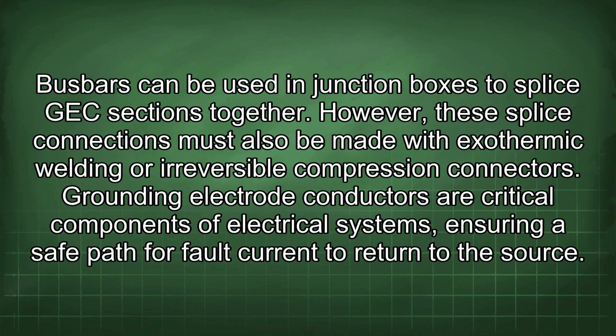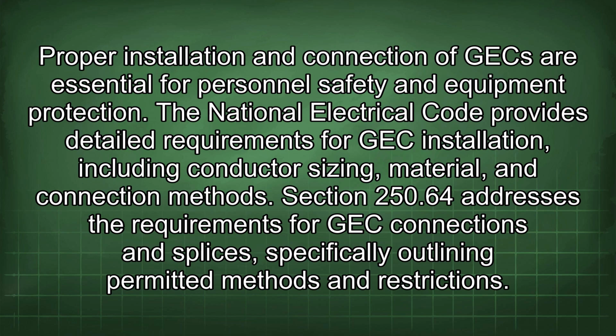Grounding electrode conductors are critical components of electrical systems, ensuring a safe path for fault current to return to the source. Proper installation and connection of the GEC are essential for personnel safety and equipment protection. The National Electrical Code provides detailed requirements for GEC installation, including conductor sizing, material, and connection methods. Section 250.64 addresses the requirements for GEC connections and splices, specifically outlining permitted methods and restrictions.